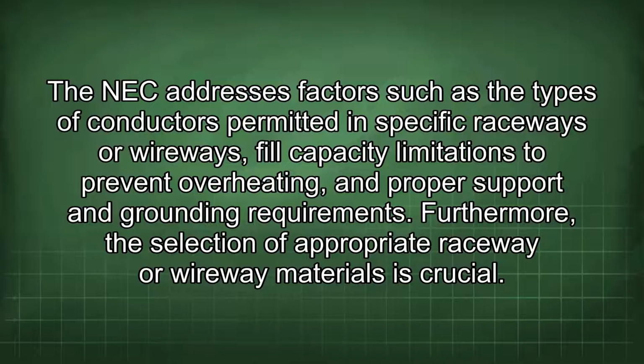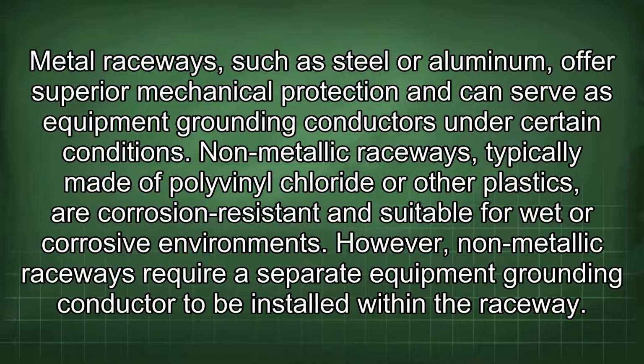Furthermore, the selection of appropriate raceway or wireway materials is crucial. Metal raceways, such as steel or aluminum, offer superior mechanical protection and can serve as equipment grounding conductors under certain conditions. Non-metallic raceways, typically made of polyvinyl chloride or other plastics, are corrosion-resistant and suitable for wet or corrosive environments. However, non-metallic raceways require a separate equipment grounding conductor to be installed within the raceway.